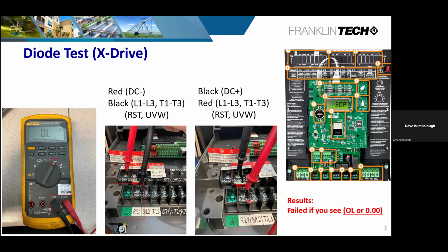What we're looking for is a value. Usually it's going to be somewhere between 0.2 and about 0.5, 0.6, something very small. You're going to see a value. What you do not want to see is what we're showing you here on this meter. It says OL. That means over the limit. So right here I've got the no-go. If you see 0 on your meter when you're doing this diode test on any of these functions, or you see OL, that means that diode has failed. And that will indicate whether we had a problem on the input side, the output side, or both. We could have had a problem on both sides. So that helps us try to identify where the potential issue may have come from.